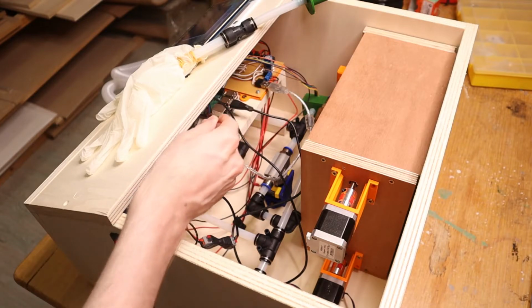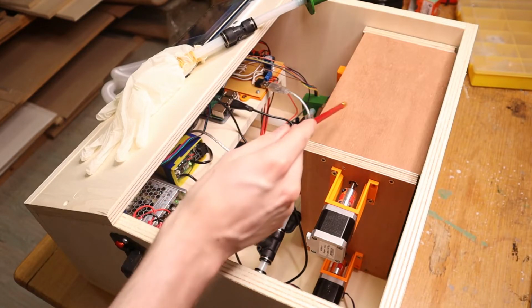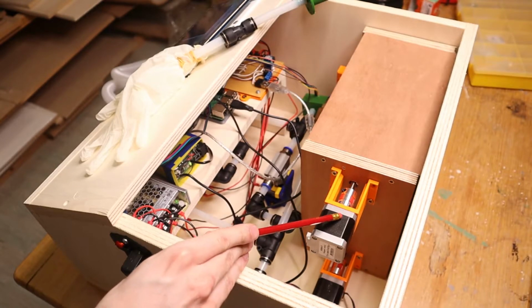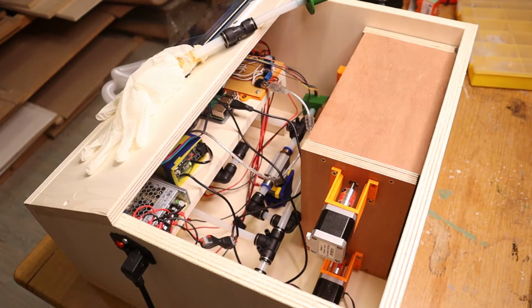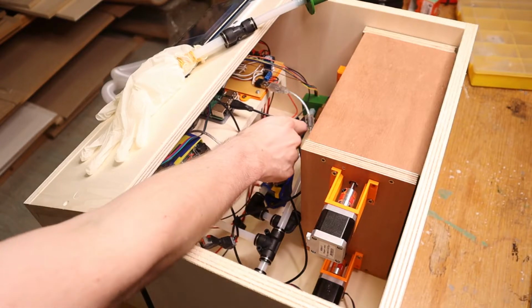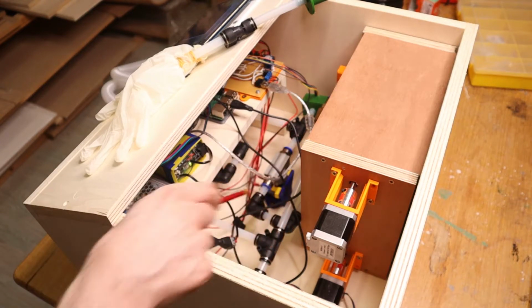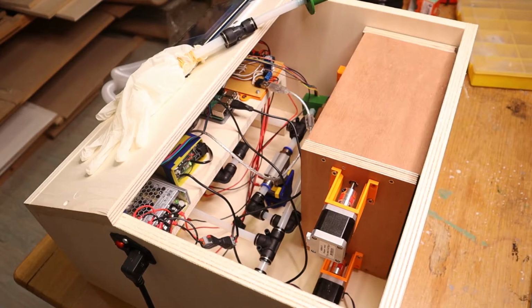So up here we have all of the electronics. In the back here we have the pump module driven by the stepper motors. And this pump module gives the force required to move the gases around to the right places. And then on the lower level here we have the valves and the tubes that direct the gas to go into the right place at the right time.